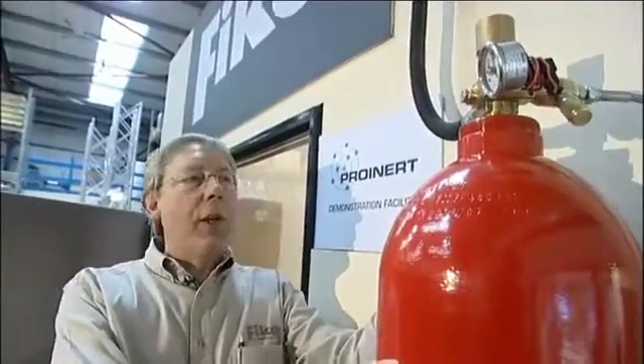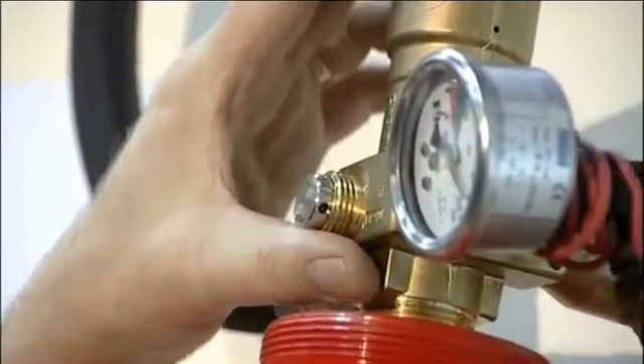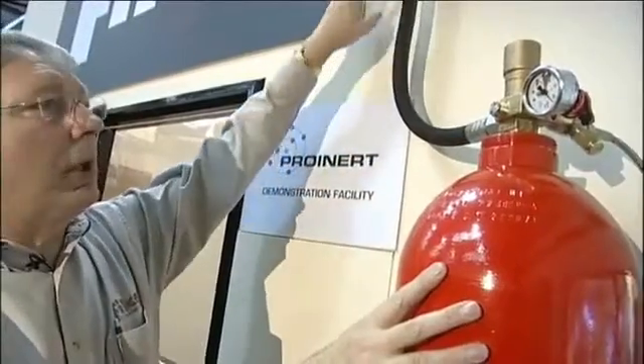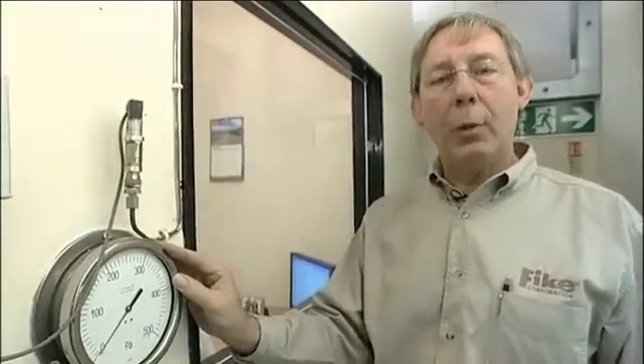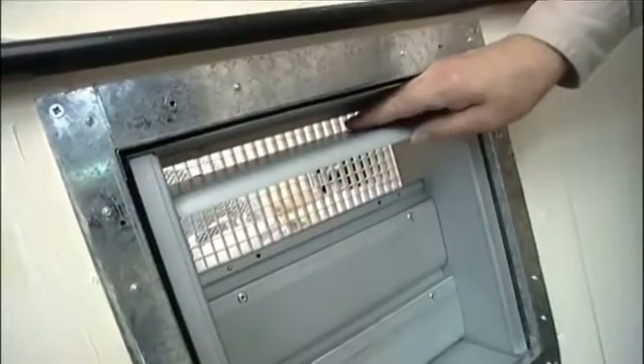An 80-litre cylinder filled with 300 bar, one patented Proinert valve, which will reduce that 300 bar to 42 bar for discharge away into the system. This instrument is going to indicate to you the sort of pressure we're going to be seeing in the room. We don't want to cause any damage in the room, so we have to limit the pressure, and to do that we use an overpressure vent.